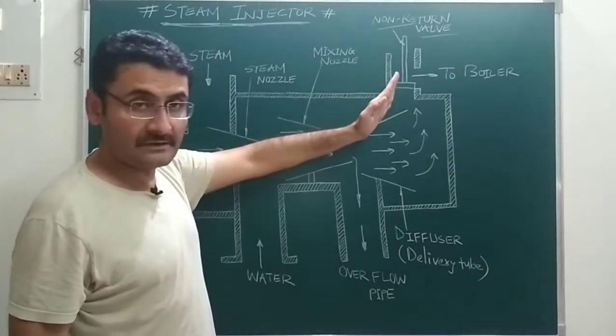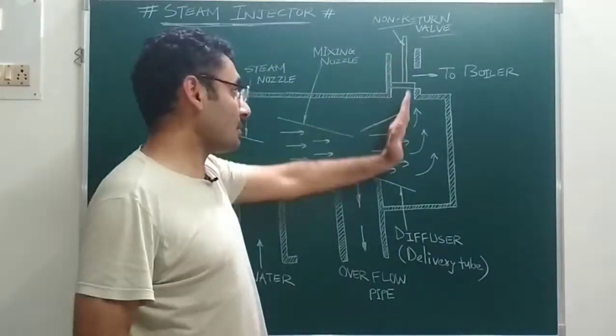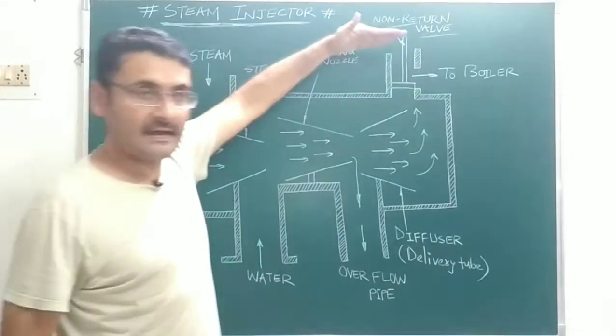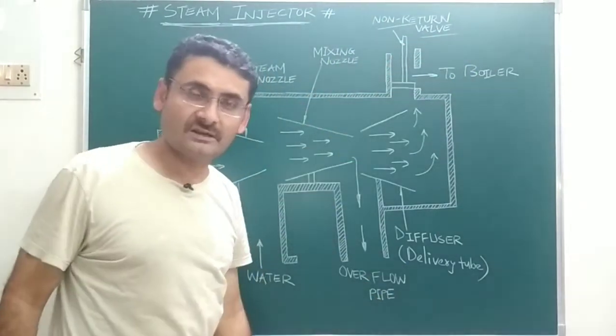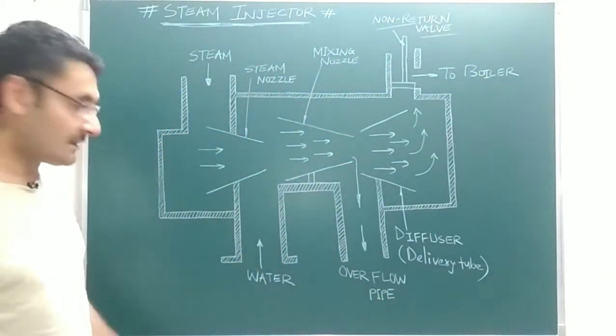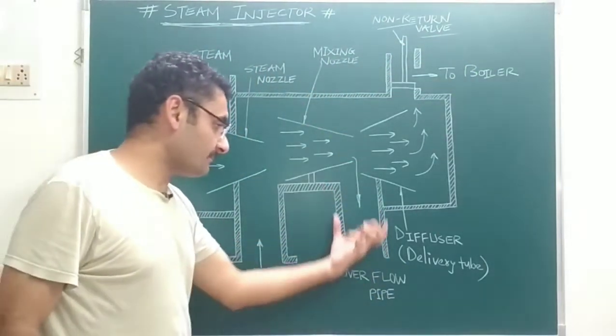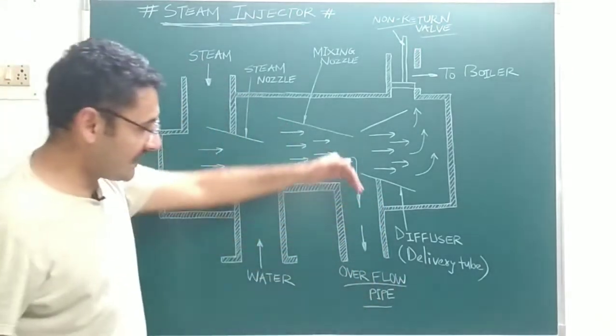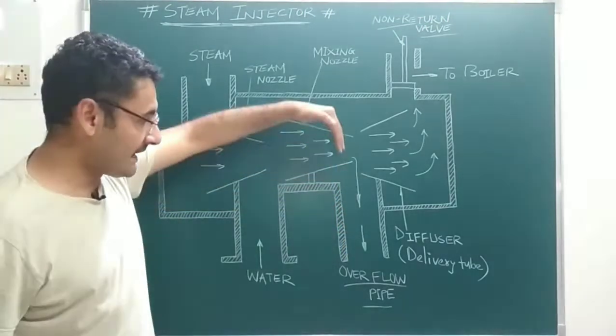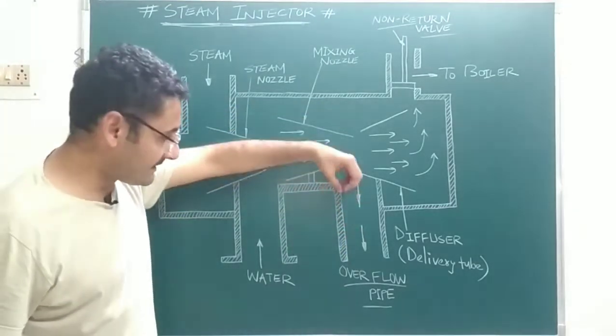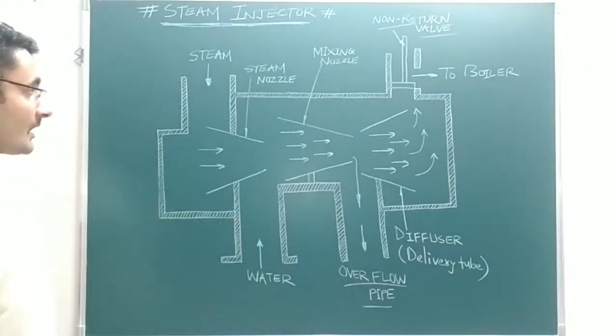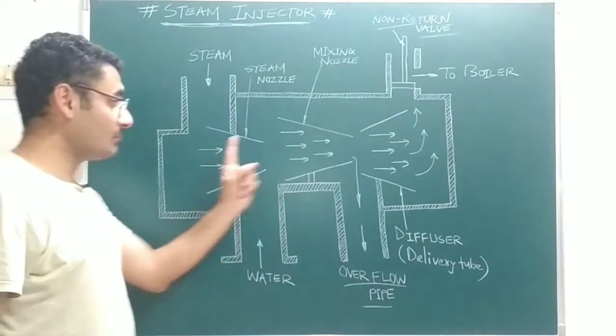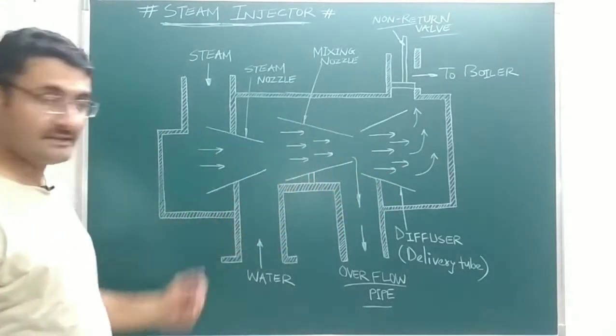The outlet is connected with a non-return valve, which opens only when the water pressure is sufficiently high — at that point it lifts upward and allows high-pressurized water to be supplied to the boiler. The steam injector also has an overflow pipe, through which any extra amount of water is removed.